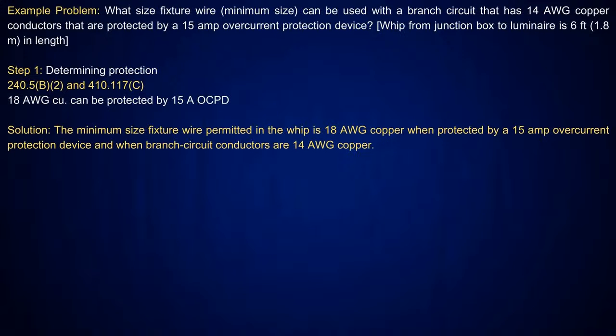This is just showing size and fixture wires here and how they can be used with a branch circuit that has number 14 conductors that are protected by a 15 amp overcurrent device, and we have a whip from the junction box to the luminaire. Now, that junction box right there, you can call it a junction box, but it's also an outlet.